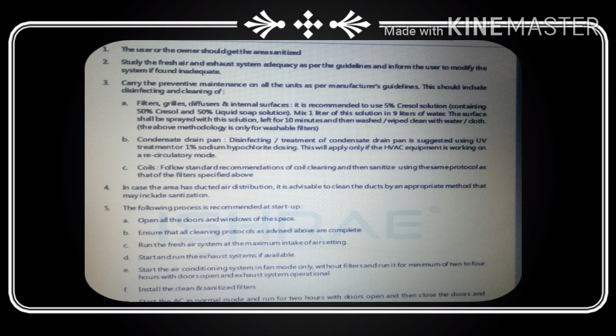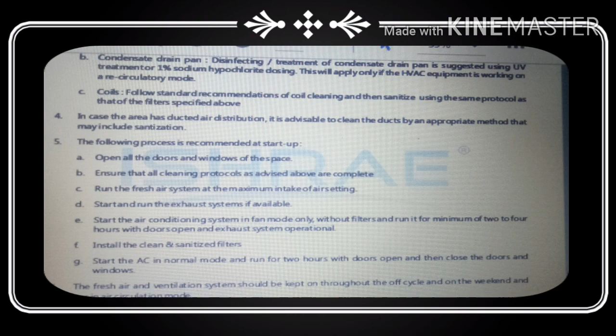The following process is recommended at startup. Open all the doors and windows of the space. Ensure that all cleaning protocols as advised above are complete. Run the fresh air system at the maximum intake air setting. Start and run the exhaust system if available. Start the air conditioning system in fan mode only, without filters, and run it for a minimum of 2 to 4 hours with the doors open and the exhaust system operational. Install the cleaned and sanitized filters. Start the AC in normal mode and run for 2 hours with the doors and windows open, and then close the doors and windows. The fresh air and ventilation system should be kept running throughout the off cycle, and on weekends and holidays, in air circulation mode. So it's very important.